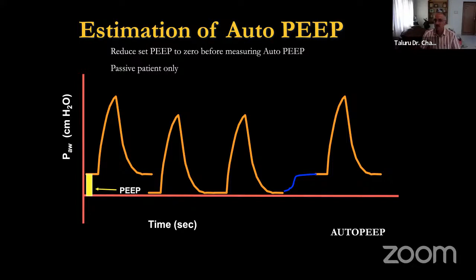For estimating the auto-PEEP in a volume controlled ventilation, first thing is make the set PEEP 0. Then put an expiratory hold for 2 to 3 seconds or 4 seconds. The pressure starts rising. This is the amount of auto-PEEP. And for the estimated auto-PEEP, we give 80% of it as the set PEEP to counteract that, so that triggering happens much faster.